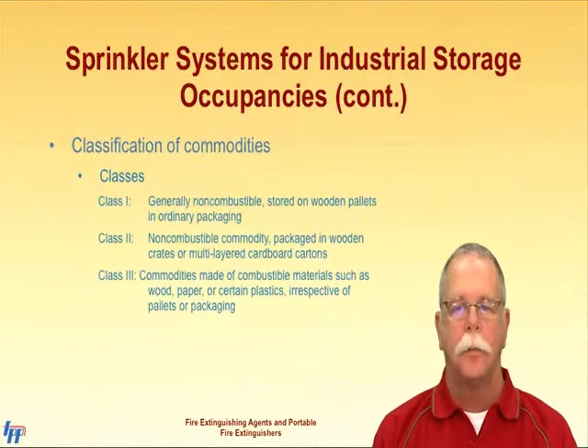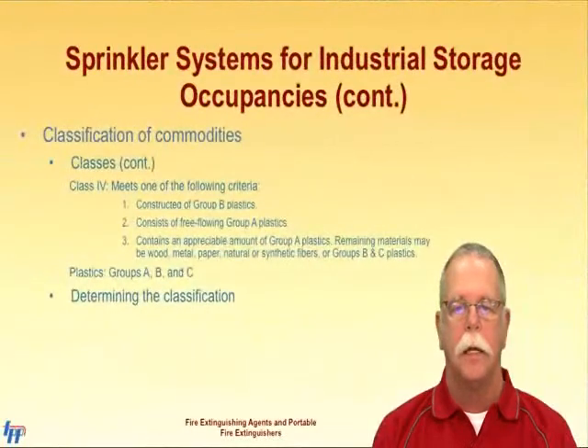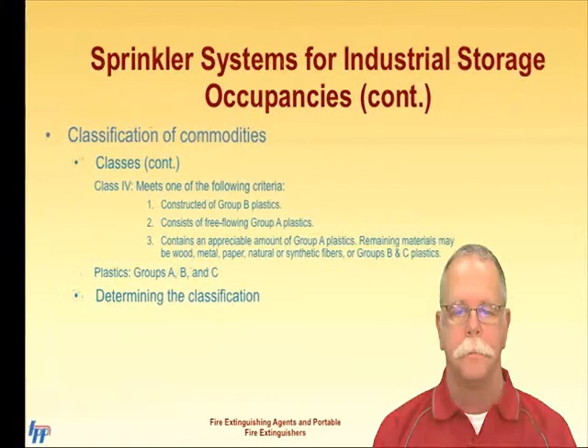The classification of the commodities that are stored is one key component to determining the amount of sprinkler protection required. The considerations that are taken into account when classifying commodities are heat of combustion, rate of heat release, and rate of flame spread. The commodity consists of the product, the packaging, and packaging aids such as shock-absorbing materials.